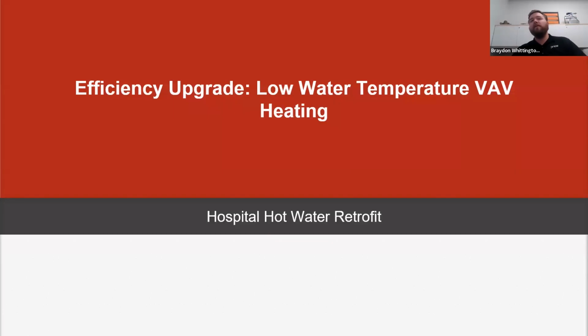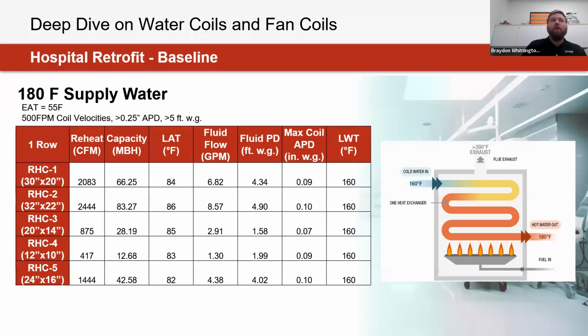So for the last portion, to combine everything: we've made the coil, we know how to calculate it, and we know some different parameters that influence its performance. The ending portion, to tie together what we've learned, is looking at a retrofit example, specifically for a hospital setting. On screen, I've listed 5 different sizes of reheat coil existing in a hospital system utilizing a conventional boiler. What we're seeing are our common targets: 180 degree entering water, entering air of 55. These are currently one-row coils within our system.